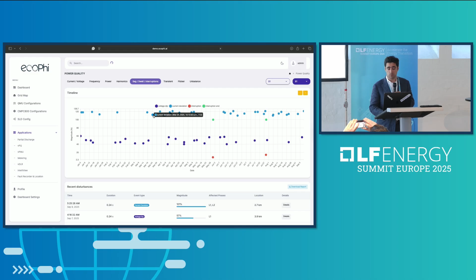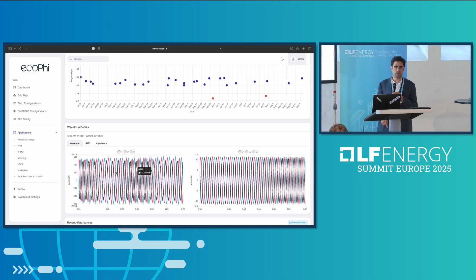It's continuous. And then virtualized power quality. As I mentioned, we measure voltage and current and every parameter that IEC standard class A requires to monitor. We monitor everything: frequency, power, sag, swell, interruption, everything, with an even tighter threshold than what the standard requires.